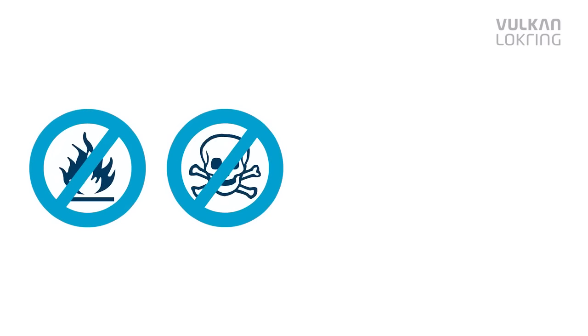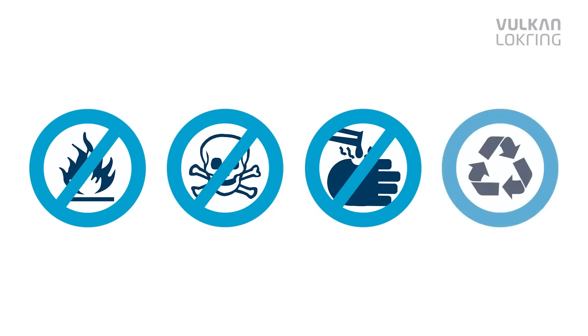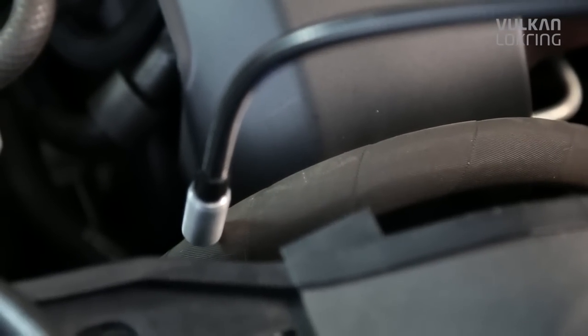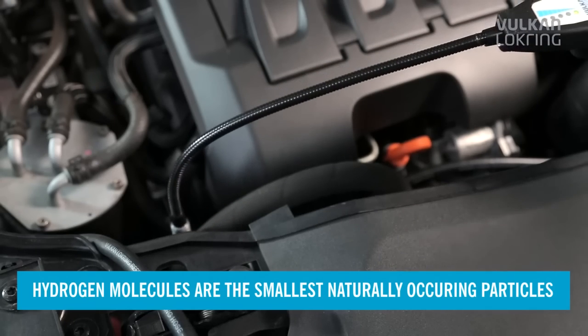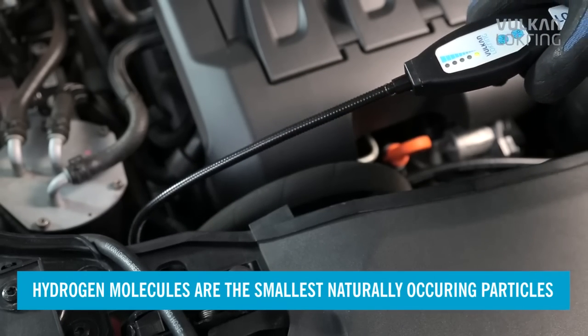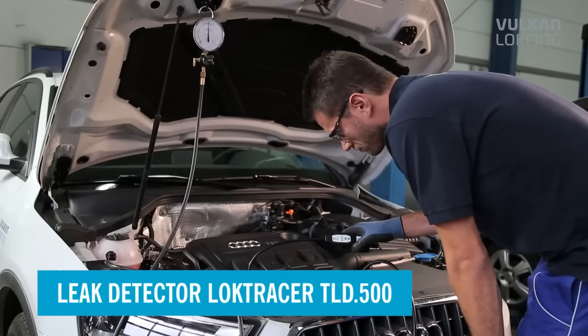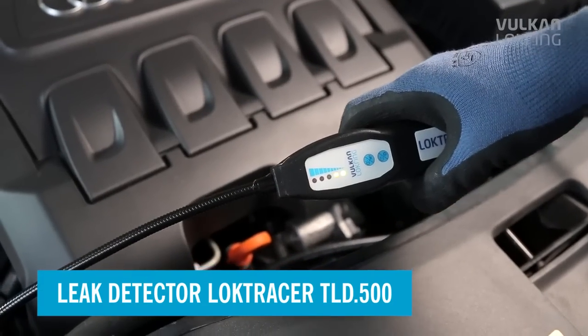Forming gas 95/5 comprises 95 percent nitrogen and five percent hydrogen. The gas is non-flammable, non-toxic, non-corrosive, and not harmful to the environment. Hydrogen molecules are the smallest naturally occurring particles and escape from even minimum leaks, so you can use the LOKTRACER TLD.500 hydrogen leak detector to trace even the tiniest of leaks reliably.